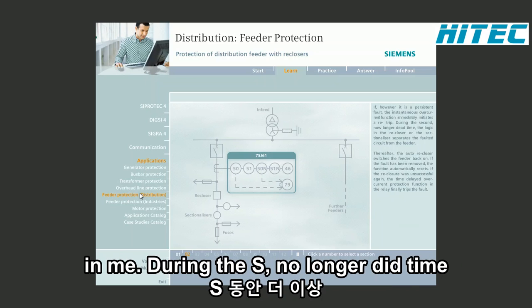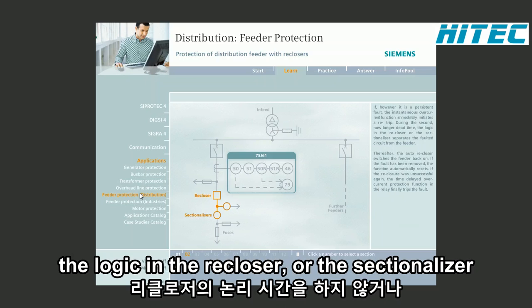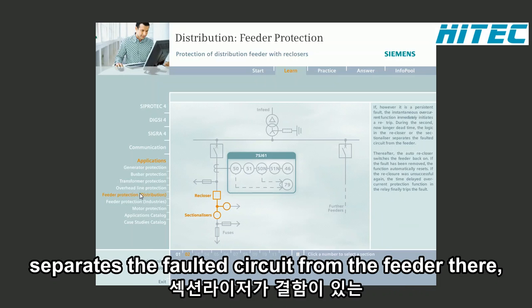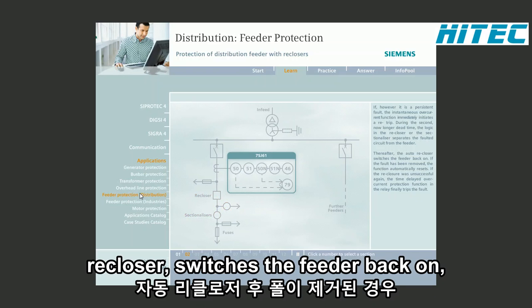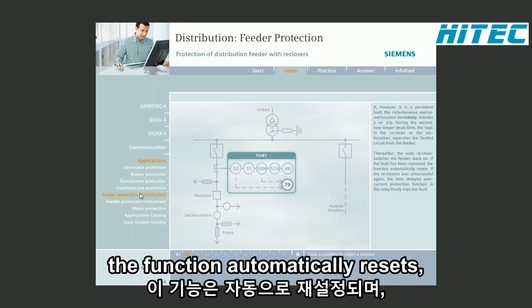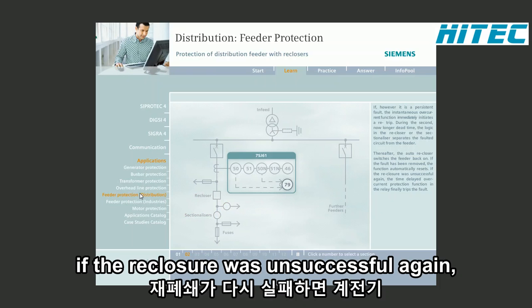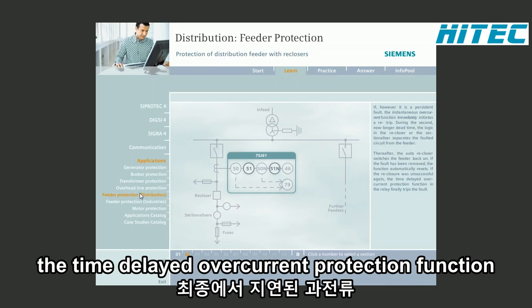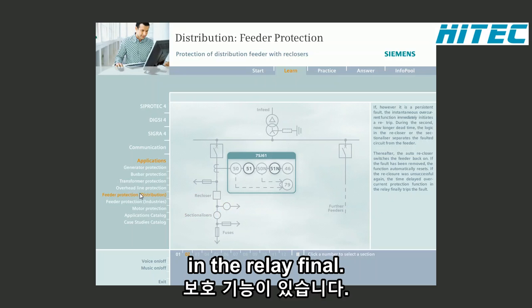During the second, now longer dead time, the logic in the recloser or the sectionalizer separates the faulted circuit from the feeder. Thereafter, the auto-recloser switches the feeder back on. If the fault has been removed, the function automatically resets. If the reclosure was unsuccessful again, the time-delayed overcurrent protection function in the relay finally trips the fault.